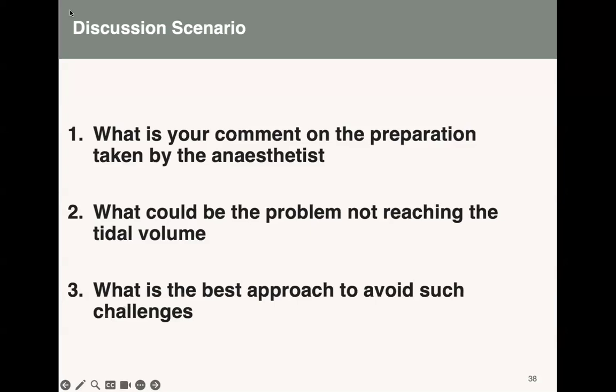Or maybe the orientation of the sensors, the flow sensor, was not in the correct manner. Somebody could have passed there earlier on, cleaning the tubings, and then they put them in the wrong way. All those challenges could be reasons why it did not set up. It could not reach the set tidal volume. That is why we said a quick machine check can really save you from such challenges, and then you have a better time to provide your anesthesia than going through such challenges. Such stress can be avoided by a simple, rapid, or quick machine check.